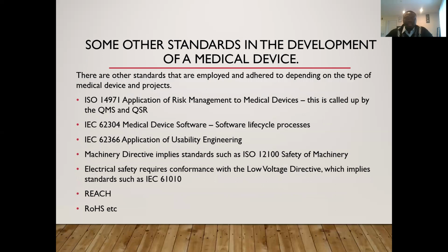So bringing it down, there are some other standards, which I won't go too deep into, which also play a role within the medical device industry, which is ISO 14971, application of risk management to medical devices. This is also called up by the QMS and then also the QSR. You have to define your risks. How are you managing your risks? And then also there's IEC 62304, which is medical device software, the software life cycle processes.